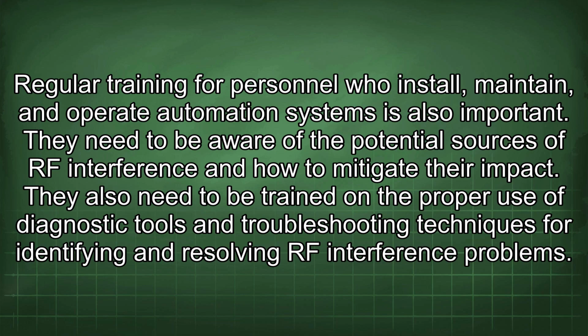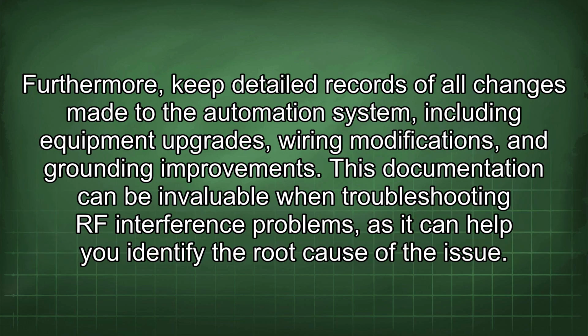Regular training for personnel who install, maintain, and operate automation systems is also important. They need to be aware of the potential sources of RF interference and how to mitigate their impact. They also need to be trained on the proper use of diagnostic tools and troubleshooting techniques for identifying and resolving RF interference problems. Furthermore, keep detailed records of all changes made to the automation system, including equipment upgrades, wiring modifications, and grounding improvements. This documentation can be invaluable when troubleshooting RF interference problems, as it can help you identify the root cause of the issue.